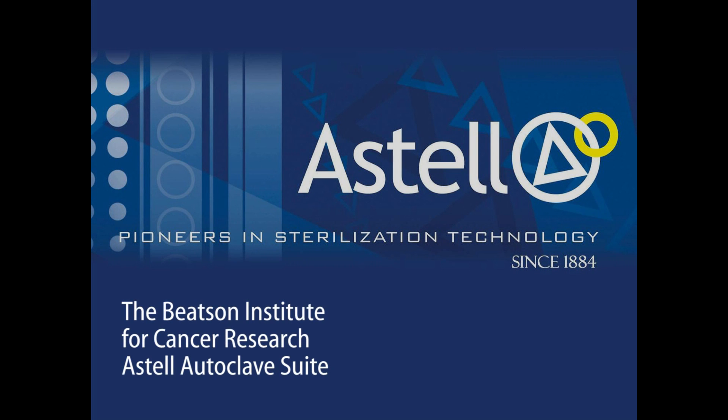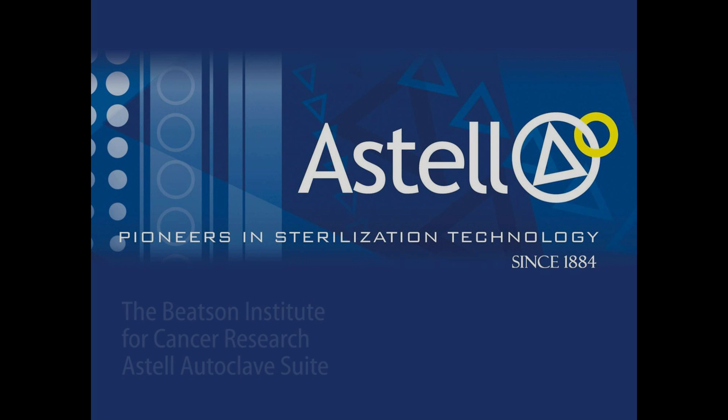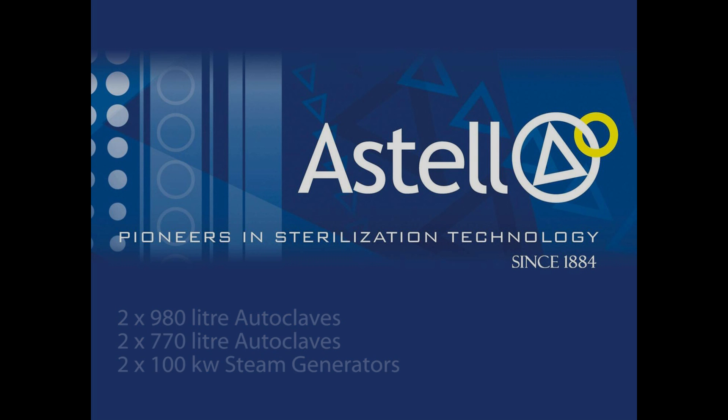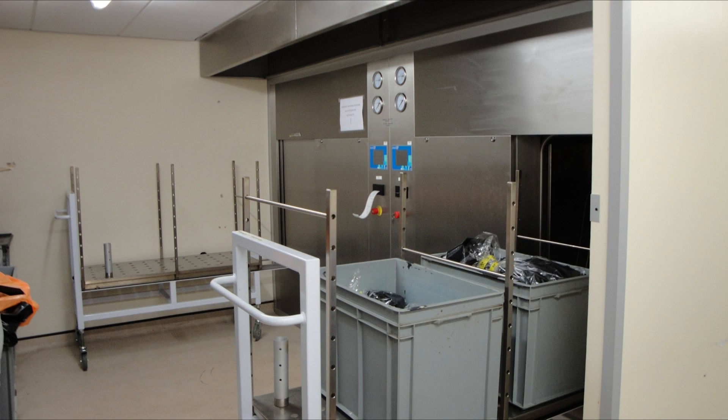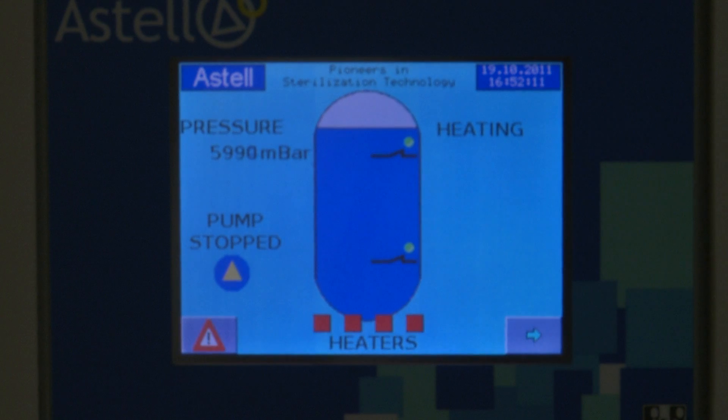The Beatson Institute for Cancer Research ASTEL Autoclave Suite. Installed in September of 2009, the suite comprises two 980 litre autoclaves and two 770 litre autoclaves, positioned in a back-to-back formation. The steam for the units is supplied by two freestanding 100kW ASTEL steam generators.